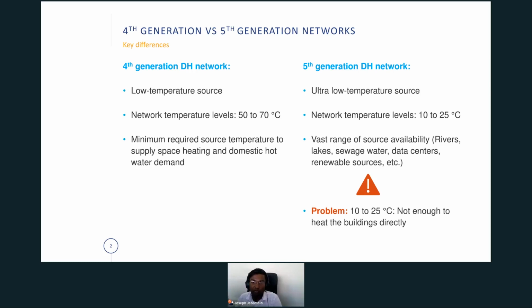If you look at ambient loop systems or fifth generation systems, we can go to ultra low temperature sources with network temperature levels between 10 and 25 degrees Celsius. So we have a vast range of source availability — we can use rivers, lakes, sewage water, data centers, and so on. But the problem is we only have 10 to 25 degrees Celsius, which is not enough to heat the buildings directly. So we need heat pumps or building-side source equipment, which are necessary in fifth generation systems.